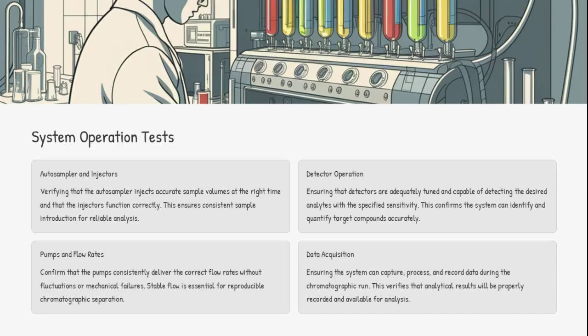System operation tests confirm that the autosampler injects accurate sample volumes, detectors are adequately tuned, pumps deliver correct flow rates, and the system can capture, process, and record data effectively. These tests ensure the system can perform chromatographic separation and analysis reliably.